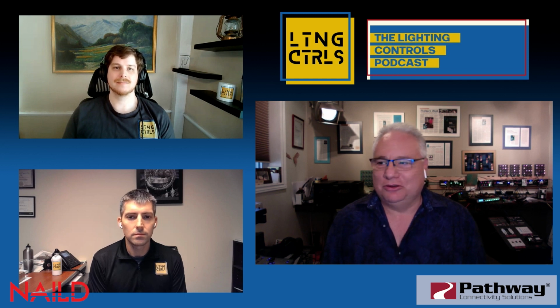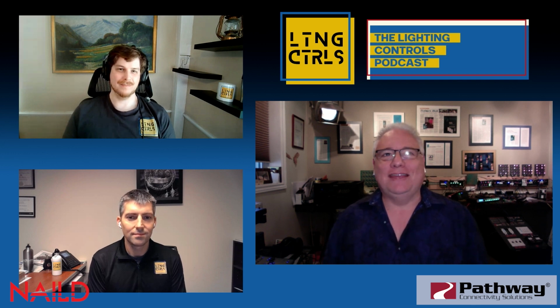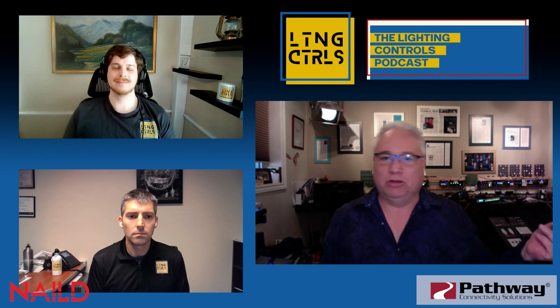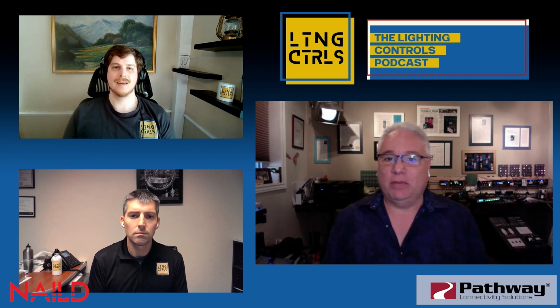Your time to last packet is always about 25 milliseconds. So it just keeps coming at you. Whereas with the kinds of things that happen in architectural lighting, you can have a very quiet wire and somebody presses a button and the lights respond, and then they just sit there until somebody else, a completely different controller with maybe different permission, presses a button and says, please do this, and the light will either listen or not listen. Where DMX, it's like "Rah!" all the time, you know.